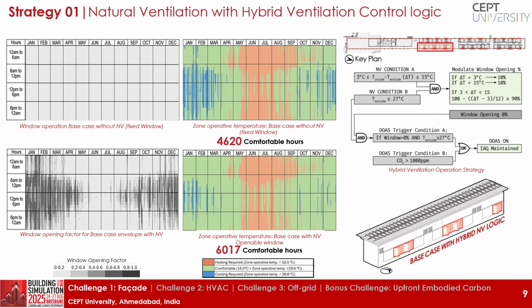The logic is simple. Windows only open if the outdoor temperature is below 27 degrees Celsius and if there is a temperature difference between inside and outside of 3 to 15 degrees. When these conditions are met, the algorithm decides what percentage of each window should open. With this approach, we reduce uncomfortable hours by 1400, demonstrating how much of an impact thoughtful natural ventilation strategies can make.